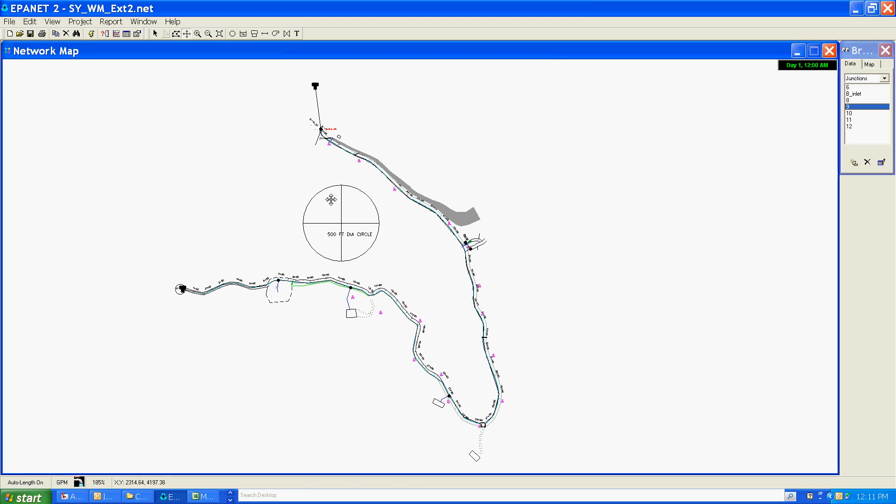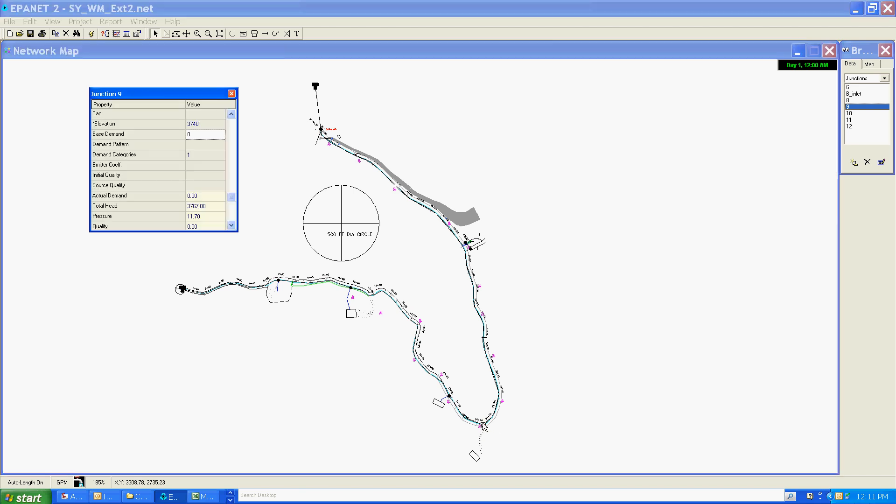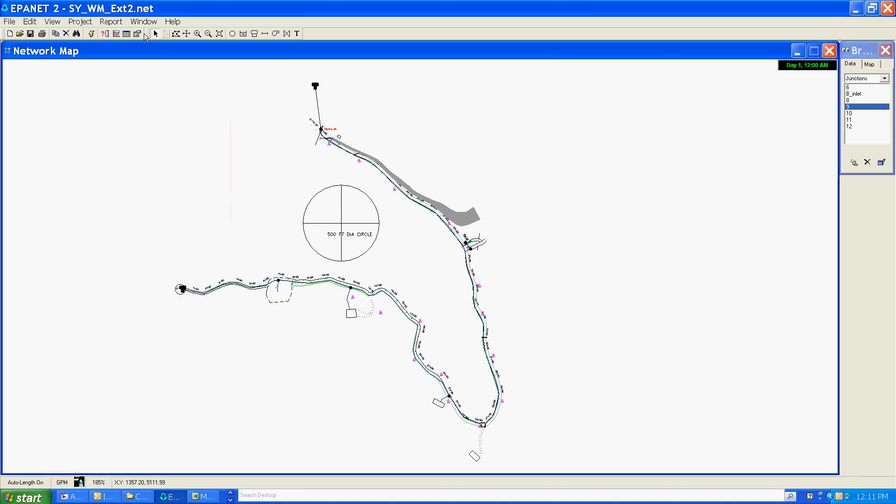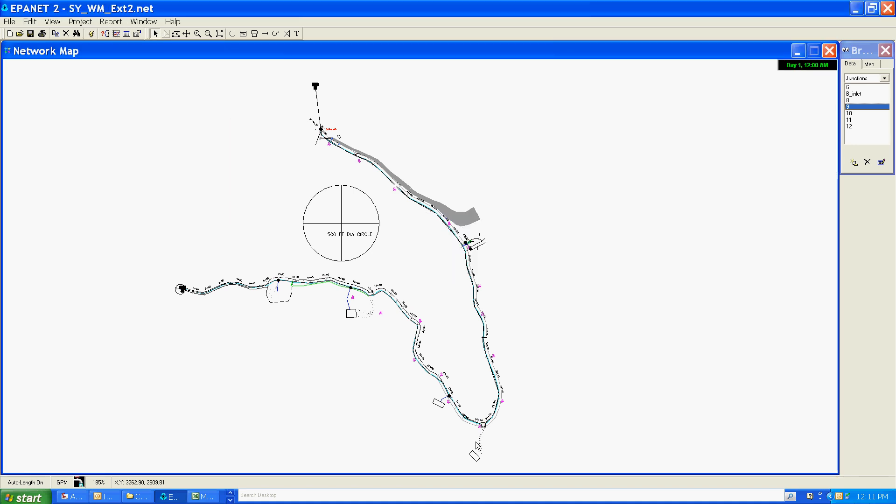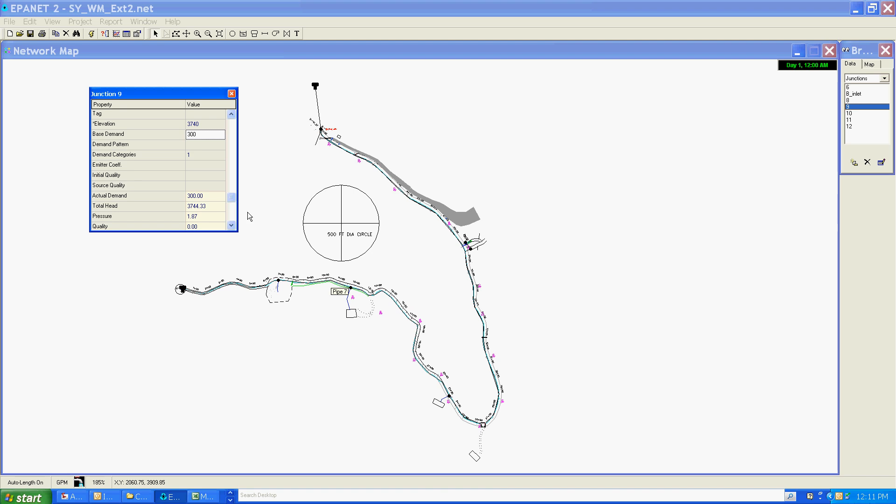So I'm going to set a demand on this node. It was zero, and if you recall, that resulted in a pressure at that point of 11.7 psi. I'm going to change that demand to 300, and I'm going to rerun the model and take a look to see what pressure we have now.